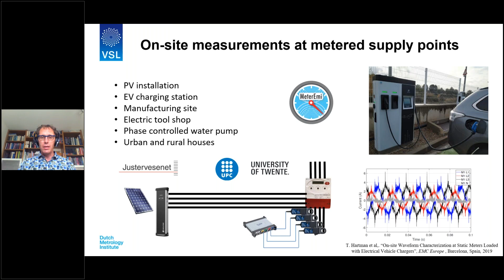At VSL, we've developed an on-site waveform recorder that goes one step further by also registering the energy consumption. This meter was shown to be more or less insensitive to interference signals and can be connected in parallel to already installed energy meters for a week or so in order to see if there's any difference in energy reading.